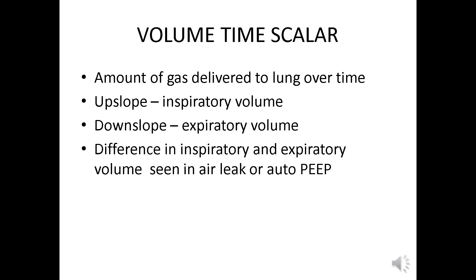We have now dealt with the pressure-time scalar and will move to the volume-time scalar. In the volume-time scalar, volume is plotted against time, depicting the amount of gas delivered to the lung over time. The up slope depicts inspiratory volume and the down slope depicts expiratory volume. A difference in inspiratory and expiratory volume indicates a possible air leak or auto-PEEP.